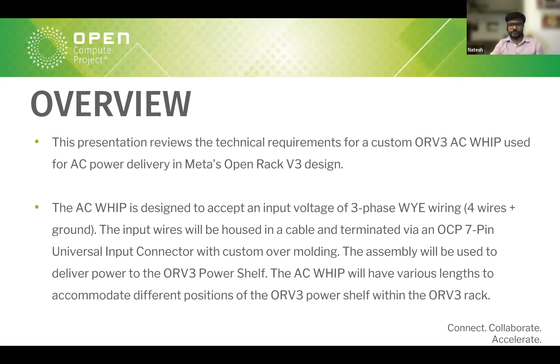So some comparisons between ORV2 and ORV3. For ORV2, you can see in the picture a bulky PDU assembly that connects the busway to the power shelves, with electronics in between for power conversion. Because of that PDU, there were potential points of failure, as well as fixed power shelf locations, which is what Daryl spoke to earlier on the rack side. You also could not expand - you were locked into two locations and couldn't move anything around.